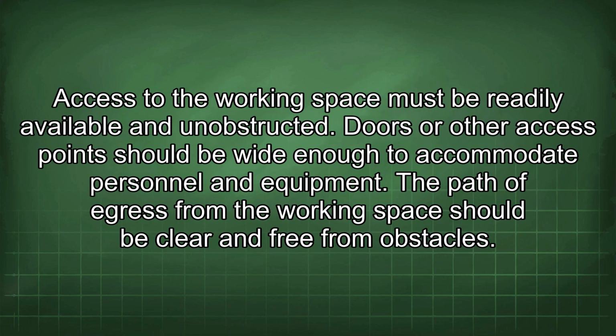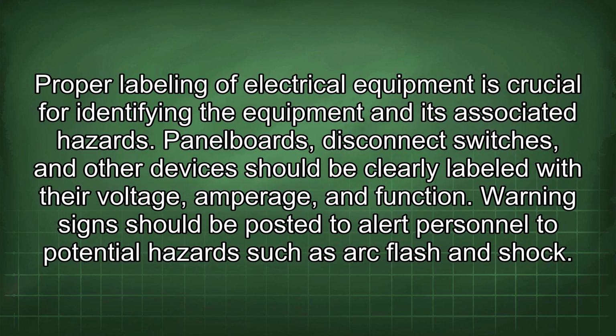Access to the working space must be readily available and unobstructed. Doors or other access points should be wide enough to accommodate personnel and equipment. The path of egress from the working space should be clear and free from obstacles. Proper labeling of electrical equipment is crucial for identifying the equipment and its associated hazards. Panel boards, disconnect switches, and other devices should be clearly labeled with their voltage, amperage, and function. Warning signs should be posted to alert personnel to potential hazards such as arc flash and shock.